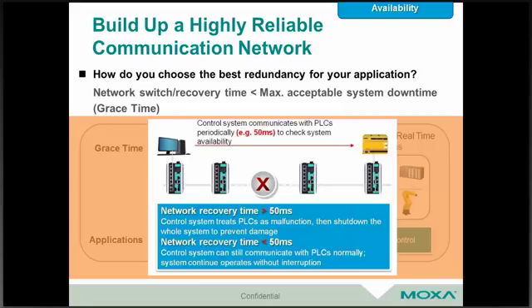This is an example that we like to show. It's essentially a control system communicating with PLCs, and those PLCs are in communication with the control system approximately every 50 milliseconds, just to check system availability and make sure everything's up and running properly. If the network recovery time were larger than 50 milliseconds, the control system would treat the PLCs as being in a malfunctioning state. If that state is detected, it will shut down the entire system to prevent damage to a production line. In that same scenario, if the network recovery time is less than 50 milliseconds, the control system will still communicate with the PLCs normally. What this means is you won't have any shutdowns and the system will continue without interruption. In this type of case, we say this is a real-time redundancy requirement.